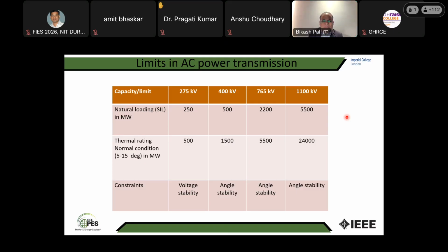Natural loading is that the loading at which the voltage across the entire transmission line length remains flat. So sending end voltage, if it is 275 kV or 400 kV, receiving end voltage also will be 400 kV, provided the line is loaded by this natural loading. So it is that value of the load current which, when passed through the transmission circuit, that circuit has got series inductance, and also the transmission conductors are insulated with respect to the ground. So they have line to ground shunt capacitance.